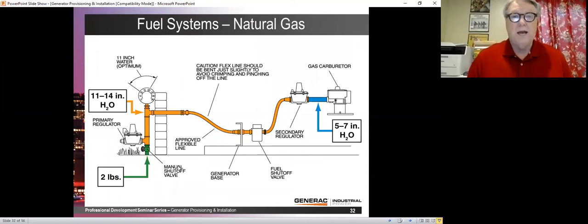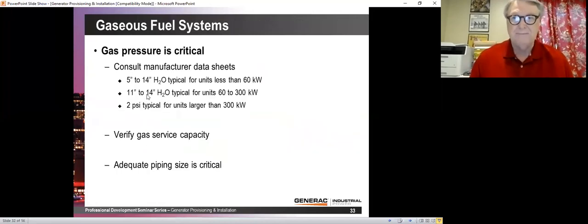Here is your natural gas system. We have covered this in previous seminars, but this is very important. You want to have a regulator near your generator, but then you want 10 feet of pipe approximately between the regulator and the generator. That acts as an accumulator just to make the fuel system more stable and to assure good starts. Now, that doesn't mean that the regulator has to be 10 foot away from the generator. You can take your piping down, put a couple of 90s in there and bring it back. You just need 10 feet of pipe to store some gas.